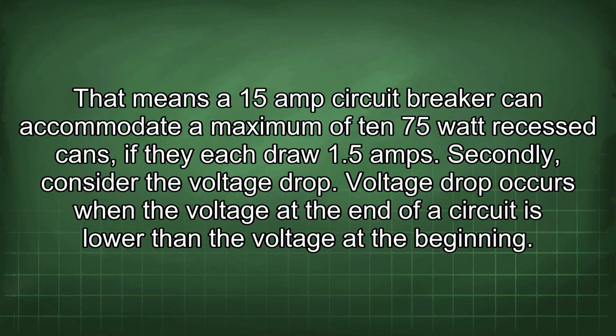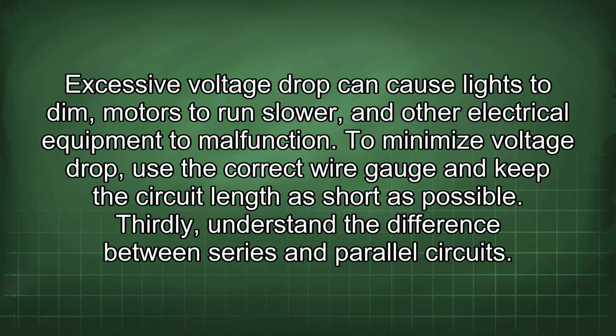Secondly, consider the voltage drop. Voltage drop occurs when the voltage at the end of a circuit is lower than the voltage at the beginning. Excessive voltage drop can cause lights to dim, motors to run slower, and other electrical equipment to malfunction. To minimize voltage drop, use the correct wire gauge and keep the circuit length as short as possible.